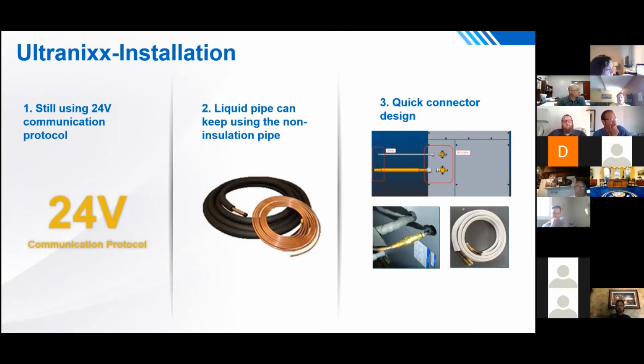The liquid line or the refrigerant piping, assuming that the old unit was 410A, you can reuse it. Best practice is always to replace that. And on the residential side, these quick connectors are becoming more and more popular. Gree does offer an option for that. It's a flare fitting of sorts. And the nice thing about them is that they are a pre-charged line set. So the trim charge for your line length is already figured into the line set. So it makes it a little bit easier for setup. Thanks, Jeff.